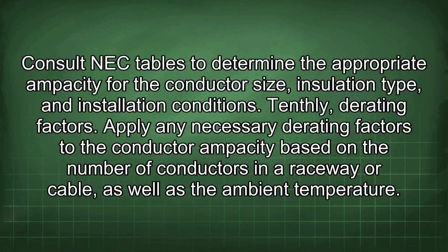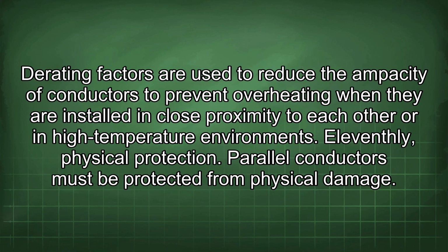Tenthly, derating factors. Apply any necessary derating factors to the conductor ampacity based on the number of conductors in a raceway or cable, as well as the ambient temperature. Derating factors are used to reduce the ampacity of conductors to prevent overheating when they are installed in close proximity to each other or in high-temperature environments.